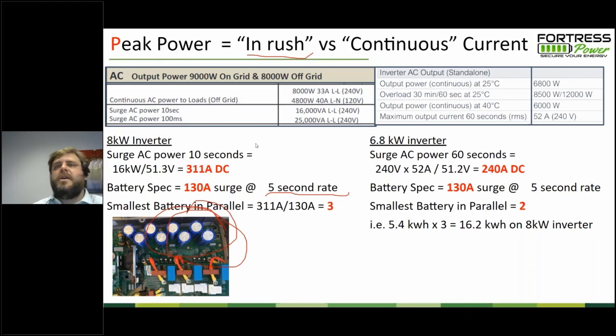And so you could go and say, all right, for this example, we have a surge rating of 310 amps, and our battery surge rating is 130 amps. And so we'll need 3 of those batteries so that the battery matches the surge rating of the inverter itself. And so you can run into a problem with too small a battery, really a missized battery, too small a battery on too large of an inverter, even when you don't have the load of the full capacity of the inverter. You could still have the capacitors inside the inverter that, when you turn on the load for the first time, absorb so much inrush current that it triggers an error in the battery management system.